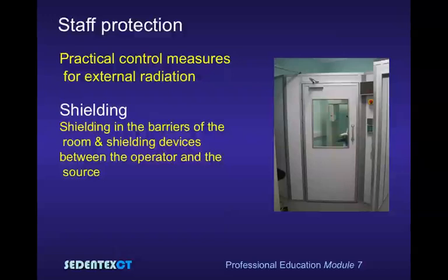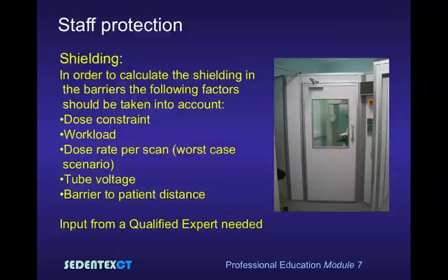In practice, however, using distance as the protection measure for members of staff with cone beam CT in a dental practice is insufficient, and we need to rely on the use of appropriate shielding in barriers and other shielding devices between the operator and the X-ray source.